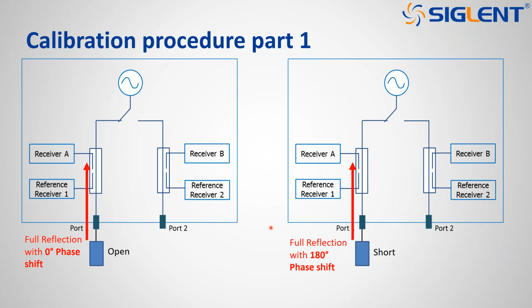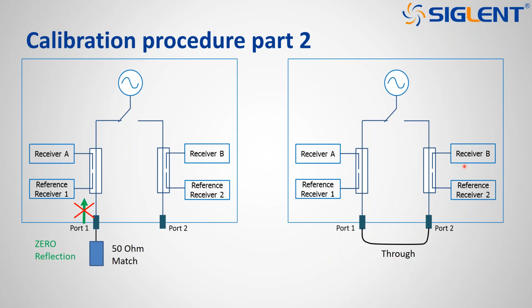Typically, the third part is that we use a very good match, so a 50 ohm match. This means we expect 0 reflection. This means everything that we measure must come from either a crosstalk issue or maybe from inaccuracies of the 50 ohms inside the unit. This can also be accurately measured, stored and put into the equations. And also for the through, we have a very well-known through, so we exactly know what we have to expect on the opposite side, on the receiver B. With all these measurements with the standards, or against the standards, we can determine and solve the error equations, and then we have a fully calibrated setup. And then the next step is that we can start accurately measuring and characterizing our devices.